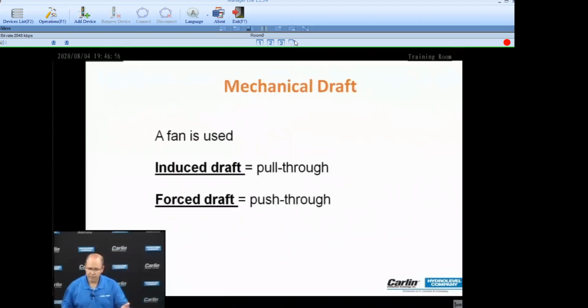Mechanical draft. Do you have the right mechanical draft system? And are you applying it correctly? Are you causing too much negative draft by inducing the draft by mechanical means? Did you really need to have that mechanical draft system? Or is it just a forced draft application? Are we pushing the flue gases through the appliance? Well, if we're pushing the flue gases through the appliance, you're set up for positive pressure, and your setup has to reflect whatever the specs are for that appliance.